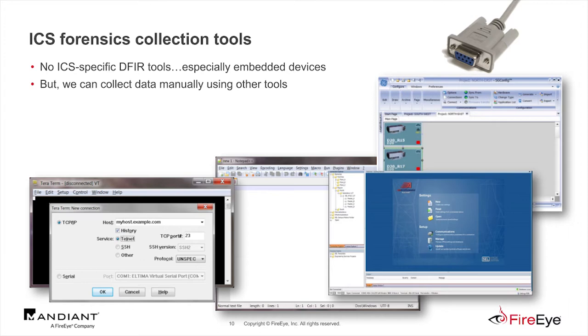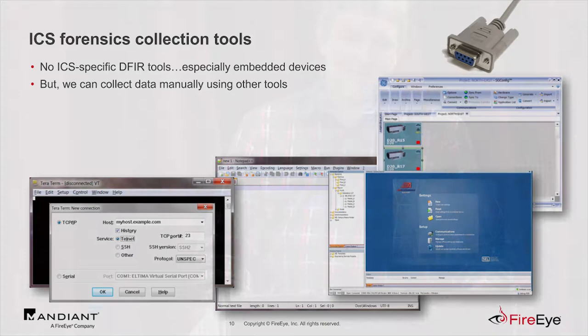If there's a suspicious thing going on — say, Jason Larson writes a PLC rootkit as an example — we know he's been in there and touched it. We don't want to reboot it; we want to find out what he's done. How do we do this collection? We have to use the tools the vendors give us and some open source tools. You use Terminal, Teraterm, or PuTTY. In this example I'm going to cover two devices — one from GE and one from Schweitzer — using those tools and a serial cable. Sometimes the only way to get information is with a good old RS-232 console cable.